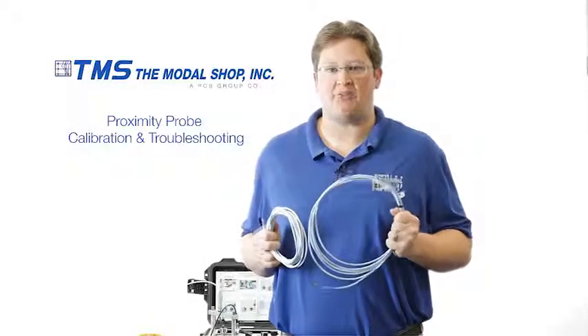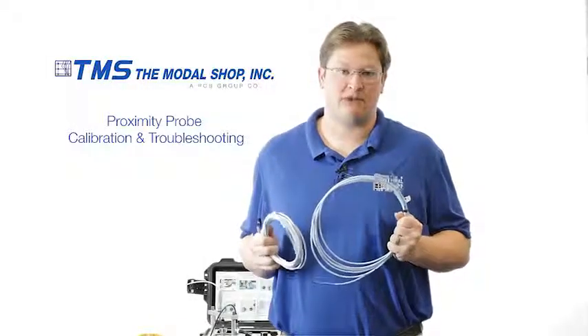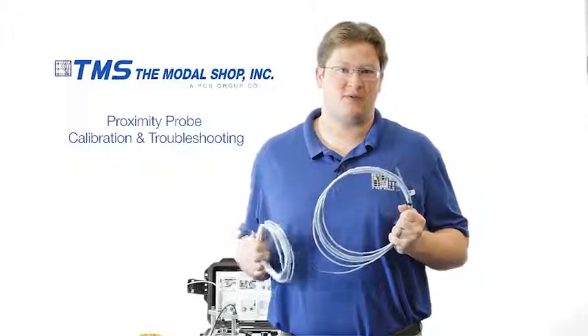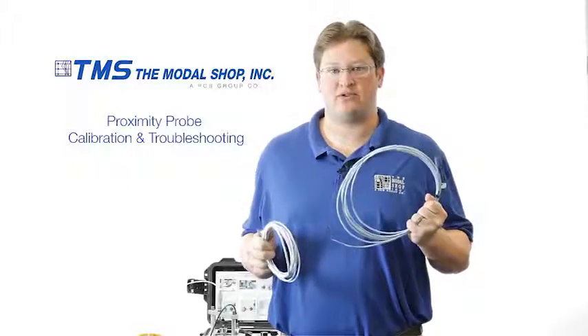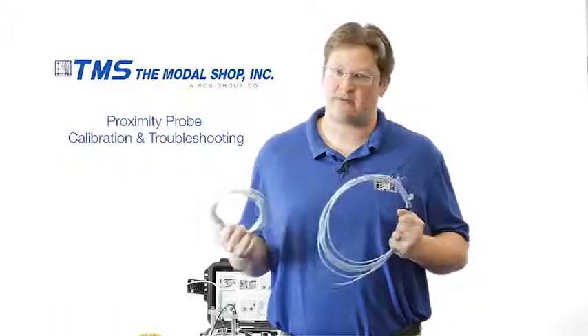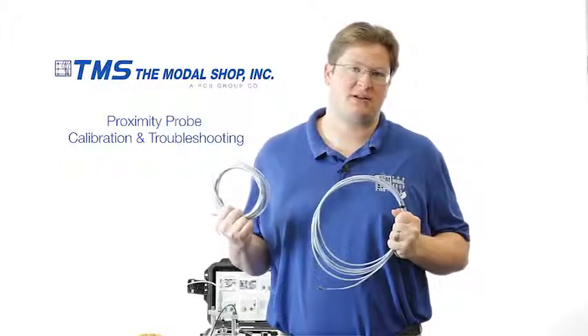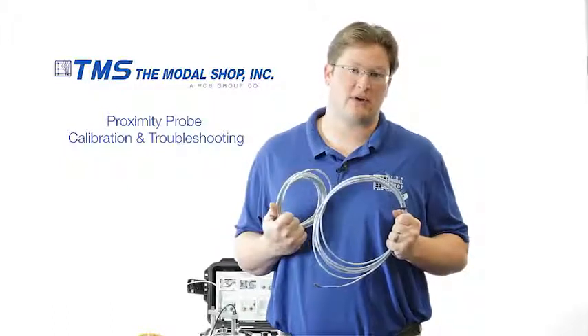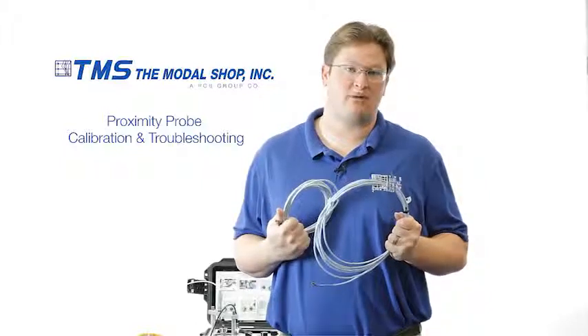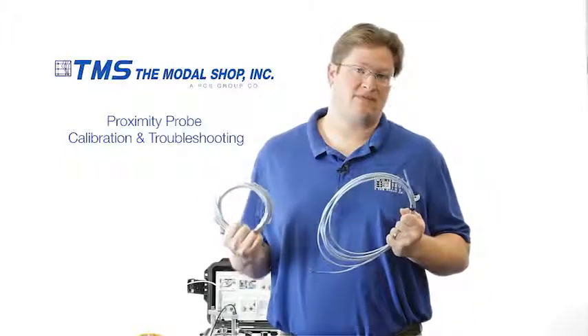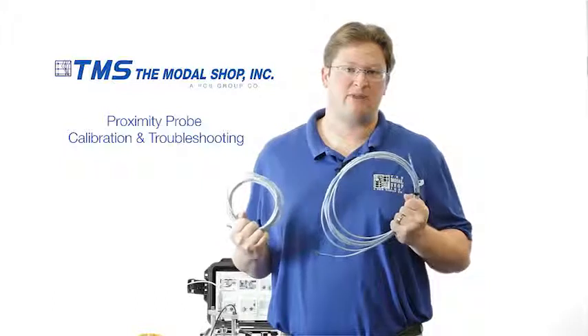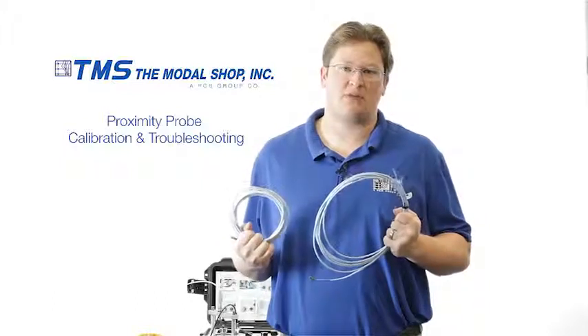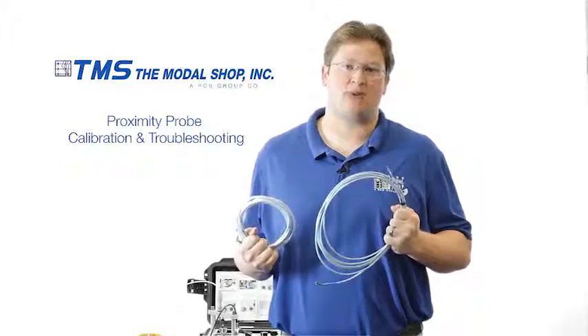You can see how a cabling error can easily occur. This is my 4-meter extension cable, and this is my 4.5-meter extension cable. They're the same color. I've coiled my 4-meter extension cable a little tighter just so I can tell the difference quickly without having to find the model number. But they're the same color and they have the same connections. And this type of mistake upon reinstallation of proximity probes can affect the dynamic output of the sensor.